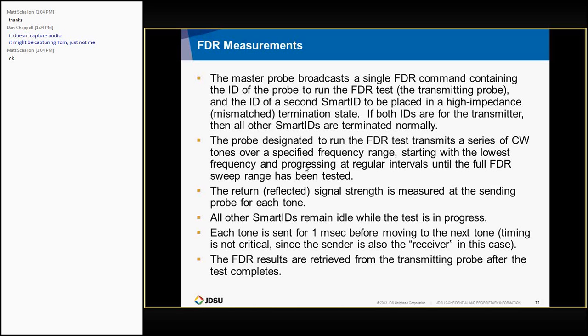When would you use that? Basically, what you're doing is generating a reference. This is done from the master probe. We'll do a single reference FDR with everybody terminated so that he sees a normal reflection pattern on the network. Then one by one, he will turn each of the slave probes to a high impedance state and run a sweep with that probe in a high impedance state. The difference between each of those and the reference sweep should be caused by that difference in the remote reflection. So the spike in the TDR at that point should make that slave probe stand out. That will give you the distance from the transmitter to that high impedance probe. That's correct. That is its purpose. Okay.